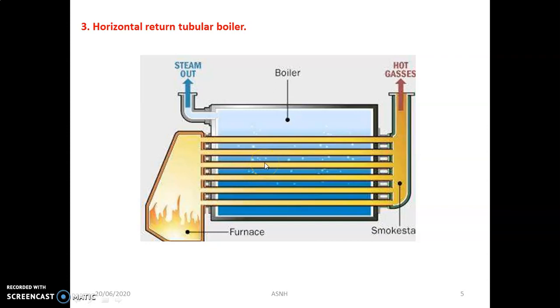Heat transfer takes place mostly by conduction and convection, as well as by radiation. The water gets heated, continuously converts into steam, and the steam exits from the top section into the steam drum. This type of boiler is mostly used in food, textile, and processing and packaging industries where the pressure requirement is in the range of 5 to 7 bar. Construction and maintenance are very straightforward with very few maintenance problems.